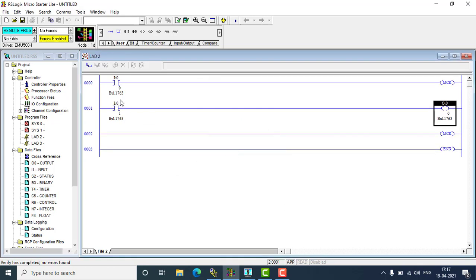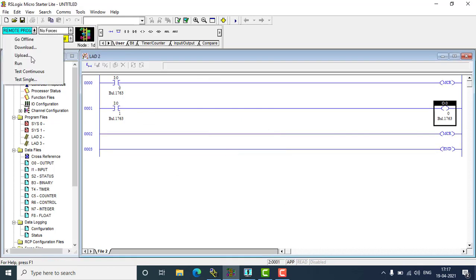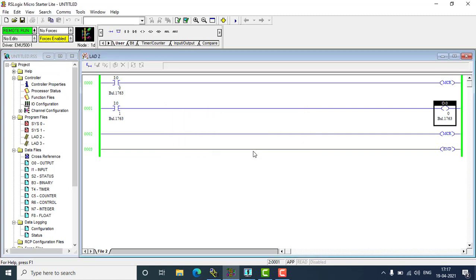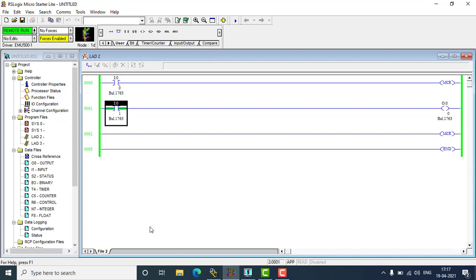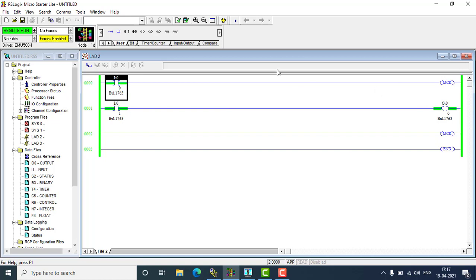At runtime, this master control can be used as an auto/manual switching mode. The program in between the MCR will be my automatic program; after the MCR I'm using the manual program. To enable the automatic program, you have to enable the master control switch. In normal condition — toggle — there will be no output because the master control switch is not enabled. Toggle the master control switch — see, now toggling the output has been turned on. That is the program control instructions in Allen Bradley. Hope you enjoyed, thank you.